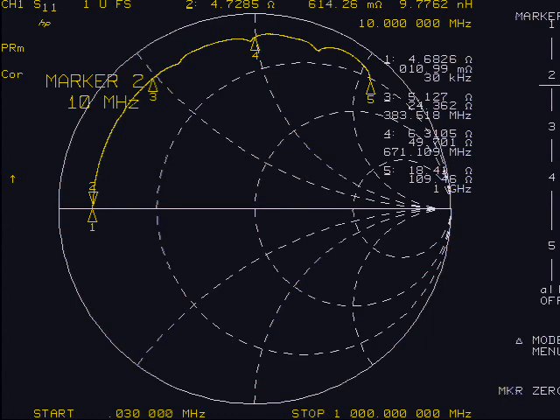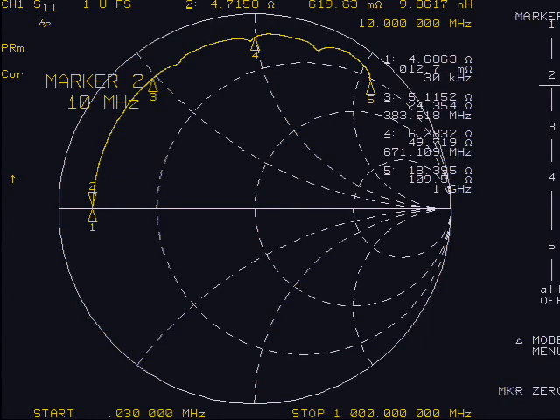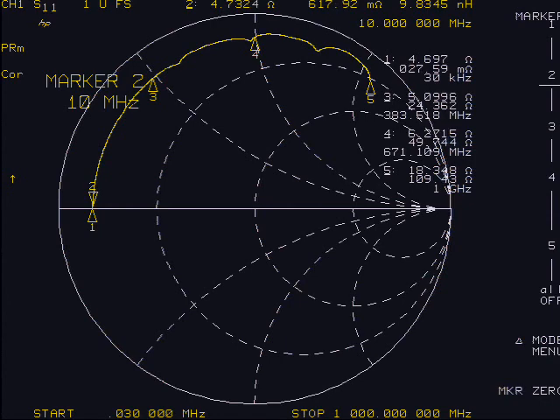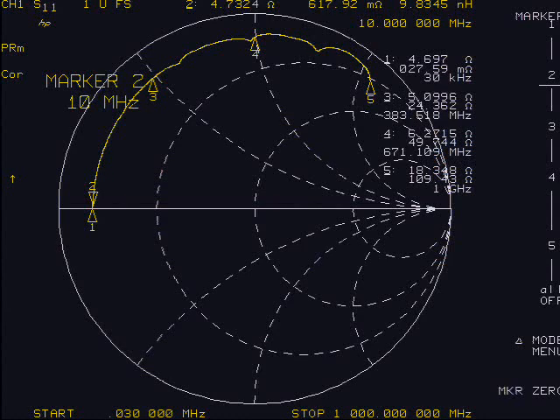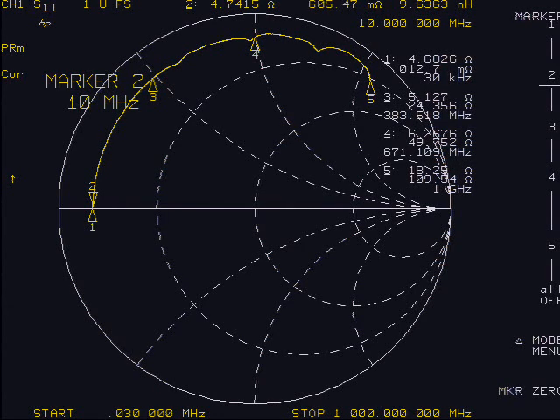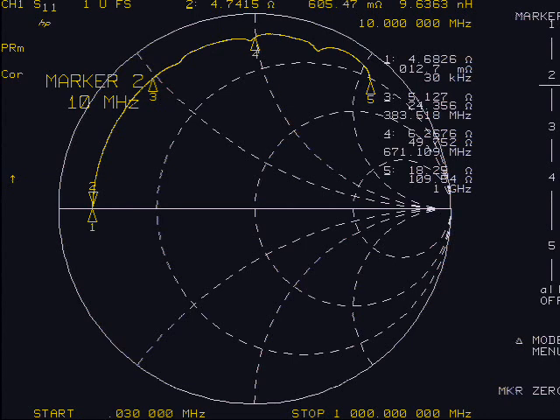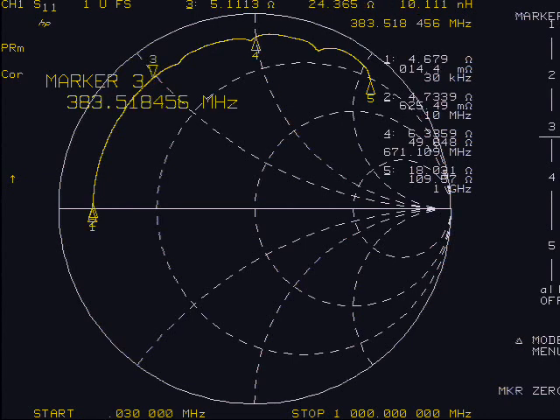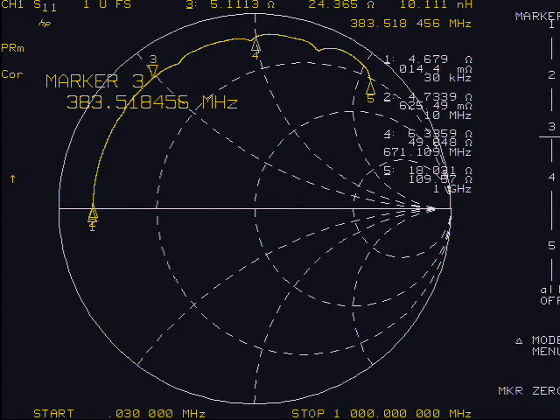We will add these points as markers 2, 3, and another marker 4 just to give us a frequency spread. By selecting each marker in succession, you can read off the specifics of the device - ohms, reactive ohms, and equivalent L or C - at the top of the screen.